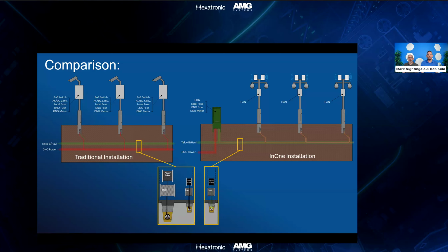Using the hybrid cable, we can use just a single duct buried to telecom standards, so only 300 mil below the surface. And as you can see from the image at the bottom of the screen there, by doing a deployment with InOne, you effectively save on around 40 to 50% of your civils because you no longer need the power trench, you no longer need the power conduit, and you no longer need the power cable.